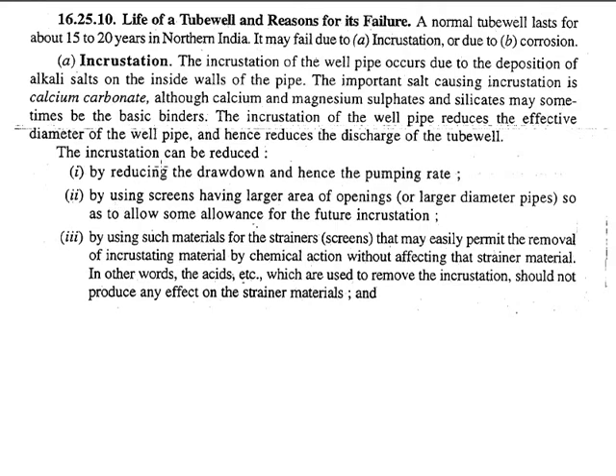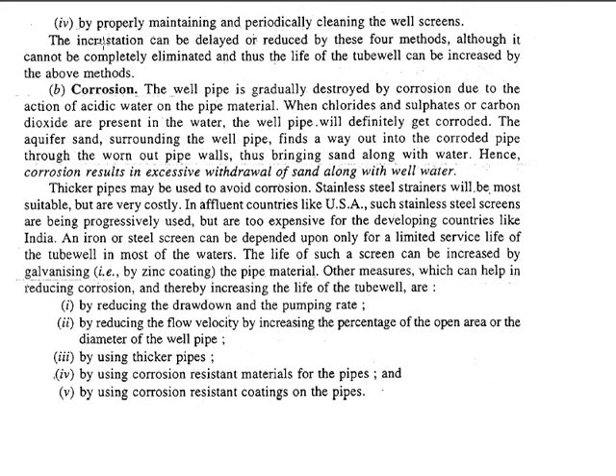Incrustation can be reduced by following certain methods: reducing the drawdown and pumping rate will certainly reduce incrustation. Using screens with a larger area of openings, or using strainers and screens, will permit proper entry through the tubewell pipe. Periodically cleaning and properly maintaining the well screen will also allow a lesser quantity of such minerals to enter the tubewells.